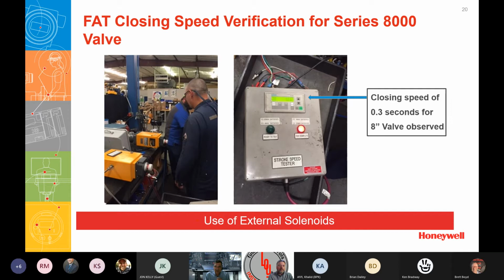You say, hey, and they say, oh, we don't do valve partial stroke testing. I said, if you don't, one of the things you should consider doing is when you de-energize, when you're going to shut down, you de-energize the solenoid, use that information as a DI to start a timer in your burner management system, and also monitor the valve close switch. So you say, hey, I de-energized, I saw the VCS, the valve close switch, made. How much time did that actually take?